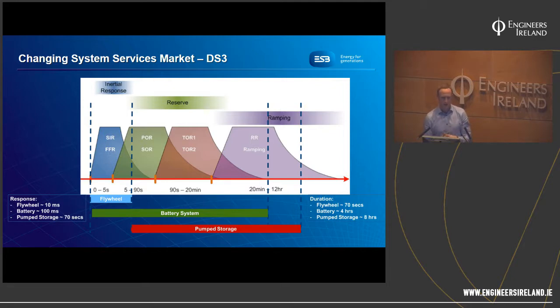Pump storage has been seen as quite high capacity and provides a lot of system support to the Irish system as well as around the world. The response time of pump storage is rather slow, circa maybe 70 seconds, which puts it outside the range of qualification for certain elements of frequency regulation. But it does have the advantage of being high energy, up to maybe about 8 hours. Of course, it's not particularly scalable, we can't really flood any more areas or have extensions like that, so there are limitations to it.